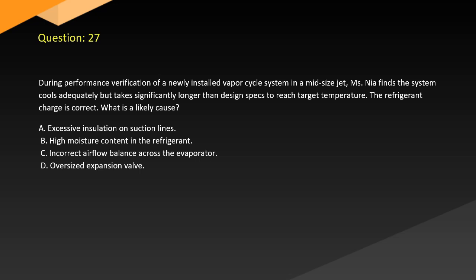Question 27. During performance verification of a newly installed vapor cycle system in a mid-sized jet, Ms. Nia finds the system cools adequately but takes significantly longer than design specs to reach target temperature. The refrigerant charge is correct. What is a likely cause? A. Excessive insulation on suction lines. B. High moisture content in the refrigerant. C. Incorrect airflow balance across the evaporator. D. Oversized expansion valve.